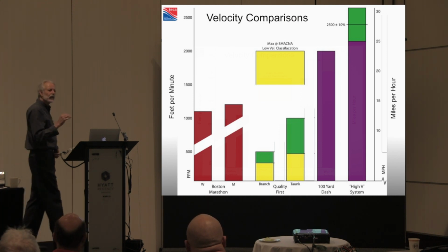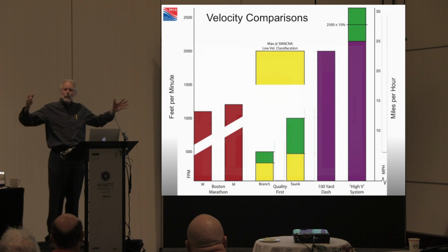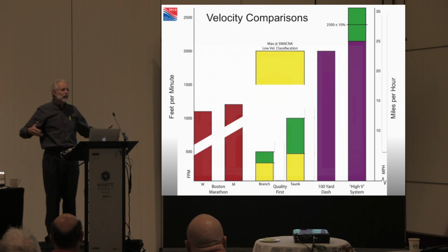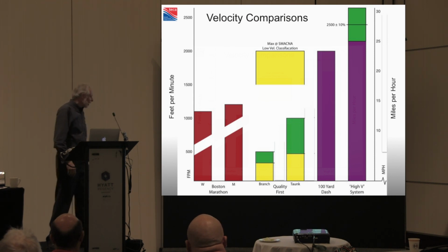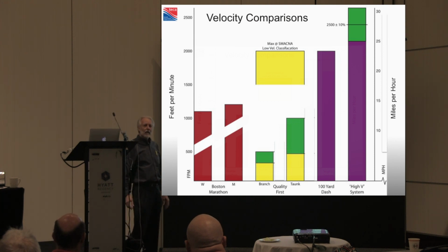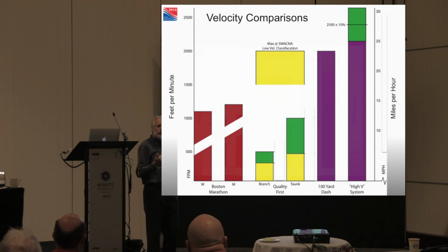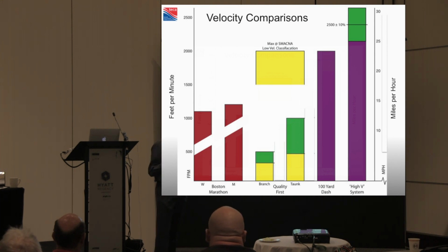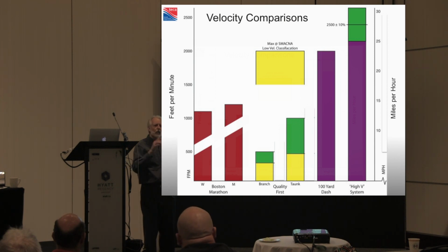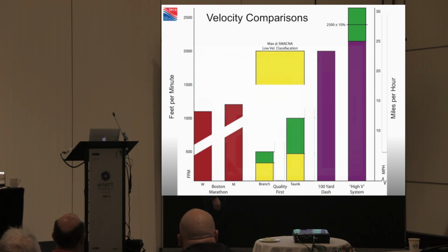We got to have this base so that you leave here with some simple, common sense message. That's how I live my life. We have speed limits in our game. You go through a school zone a little bit over the speed limit, it's $170. I just paid one of them. Speed limits in school zones used to be 15 miles an hour, maybe it's 20, I don't know what the metric is. Well, we have speed limits in our trunk ducts. You can't go more than 12 miles an hour because that's the upper limit of speed in our trunk ducts.